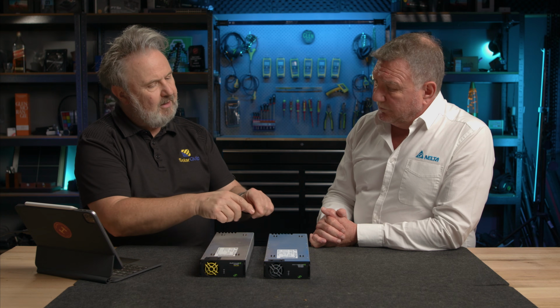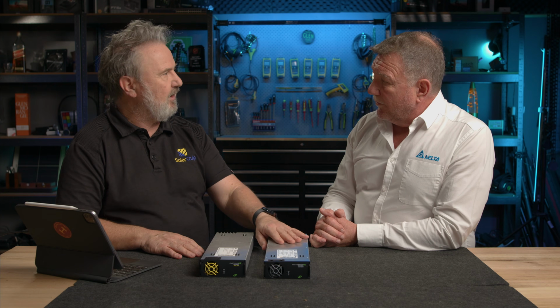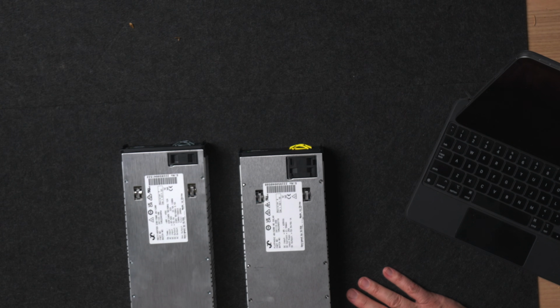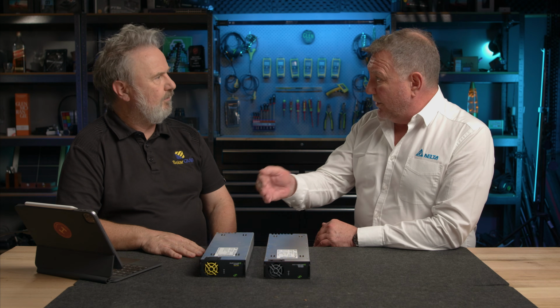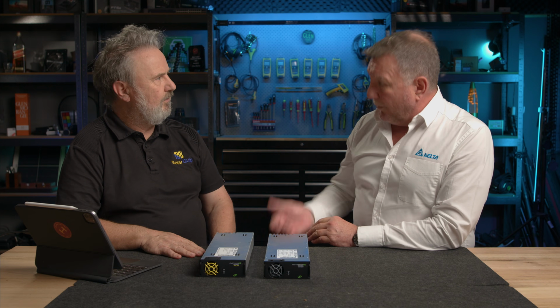So when you say load sharing, if you've got more than one, they proportionally share the whole load across the multiples? Correct, so effectively they're running very lightly most of the time. There's obviously a peak, a nice sweet spot where you're getting maximum efficiency out of the power conversion. But the good thing is, if you do lose one, your load is still maintained because typically you'll have redundancy built into the modules. So you're not going to drop the load. In other types of inverter systems, if the inverter fails, you drop the load. Whereas here we're seeing a very high level of availability.